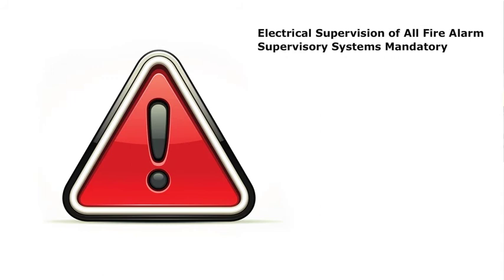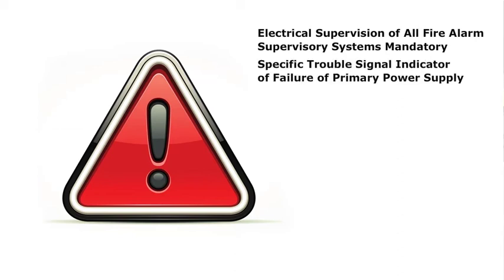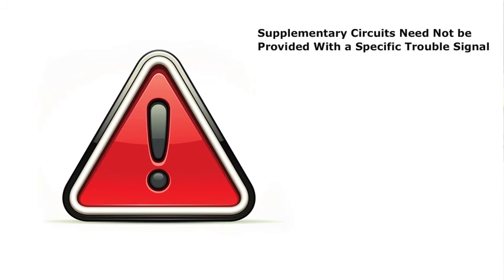It's important to note that all fire alarm supervisory systems should be electrically supervised, so the occurrence of a single open or single ground condition in the installation wiring system that prevents normal operation or causes failure of the primary power supply source is indicated by a specific trouble signal. Also, for supplementary circuits in an electric fire alarm system, it is not necessary to be provided with a specific trouble signal.